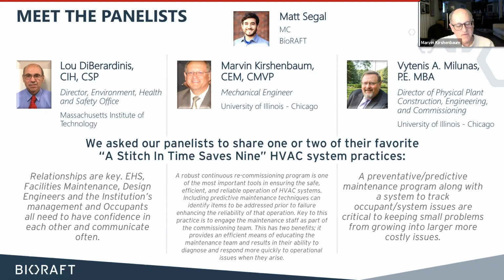They've done a number of computational fluid dynamic analyses for laboratories. If you have a spill, you can see in some cases that having high air change rates, or air distribution patterns that are set up to remove heat, can actually enhance the evaporation rate and make the situation worse, or spread the contaminant throughout the space more effectively. So I don't think there have been any new standards. I think it's something that's got to be looked at.